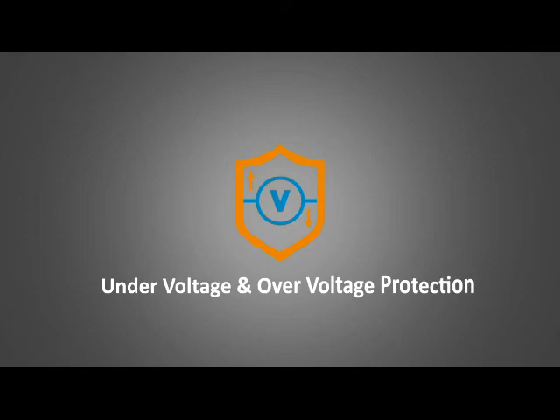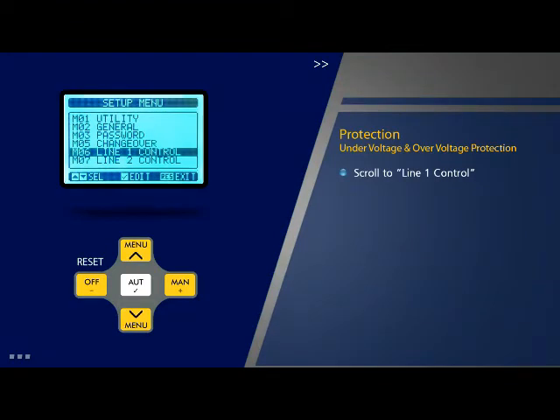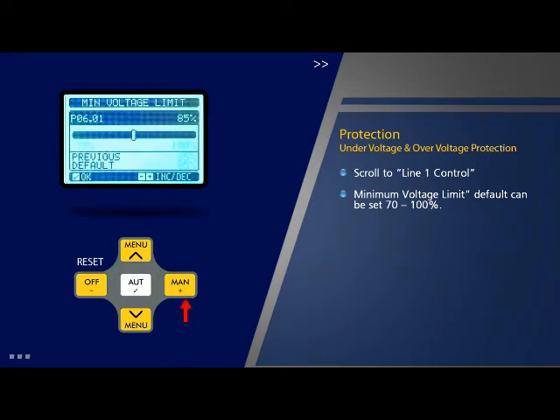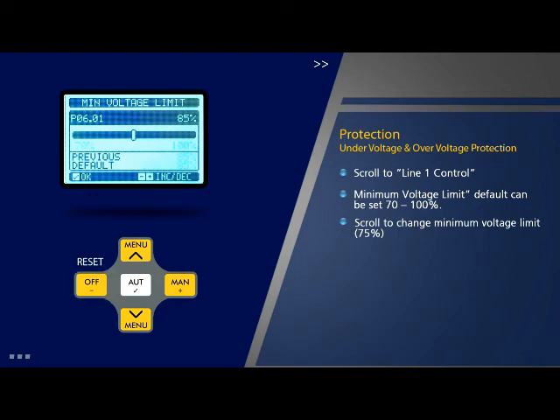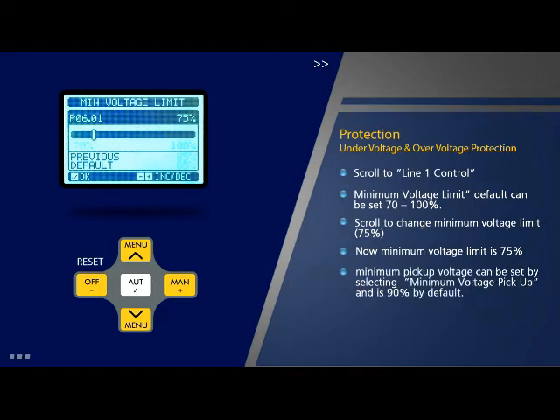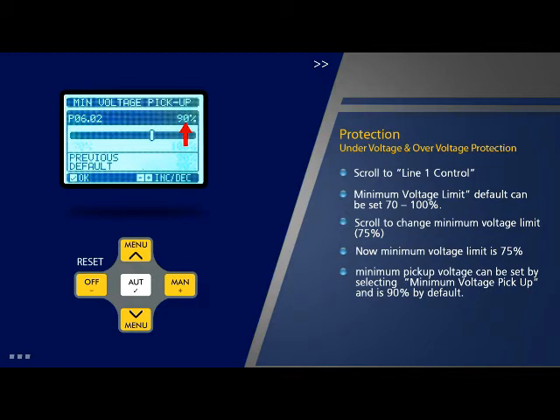Under voltage and over voltage protection: The procedure for programming related to under voltage and over voltage protection is as follows. Scroll to parameter 6 'Line 1 Control' on the setup menu page and press OK. Select the first parameter 'Minimum Voltage Limit' on this page — it is 85% by default and can be set in the range of 70 to 100%. Scroll to change the minimum voltage limit, for example to 75%, and press OK. The minimum pickup voltage can be set by selecting the second parameter 'Minimum Voltage Pickup' on the line 1 control page — it is 90% by default.